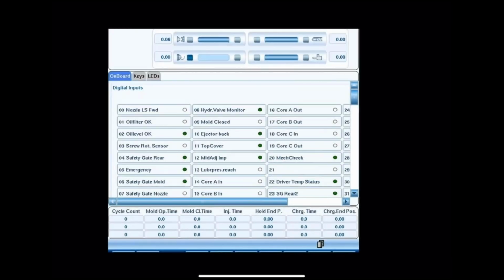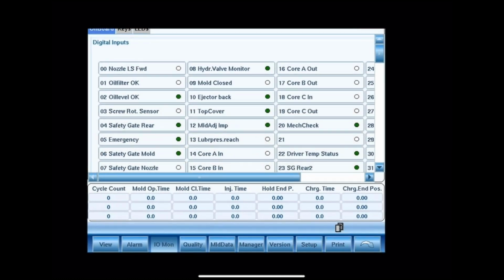IO monitor shows you all the inputs and the outputs. Now, all the outputs can be forced by just clicking on one of these little round circles. You go to the output that you want to look at. Of course, these are inputs, but you just push on the circle and it'll ask you if you want to force the output on. You have to do that with the pump disabled, the drives disabled. So you do not push the drive on button.